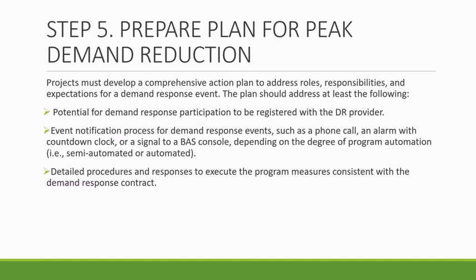Projects must develop a comprehensive action plan to address roles, responsibilities, and expectations for a demand response event. The plan should address the potential for demand response participation, such as curtailment of peak demand and the elected demand response value, or schedule values, in kilowatts to be registered with the demand response provider. The plan should also address an event notification process for demand response events, such as a phone call, an alarm with countdown clock, or a signal to a BAS console, depending on the degree of program automation.